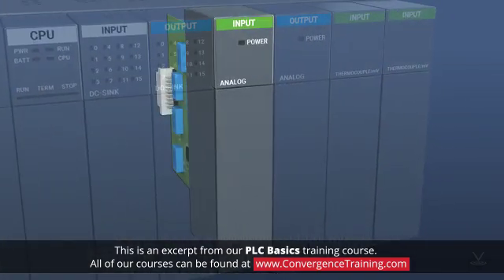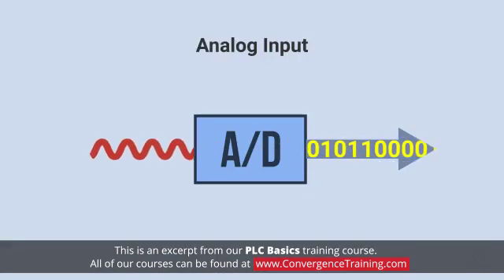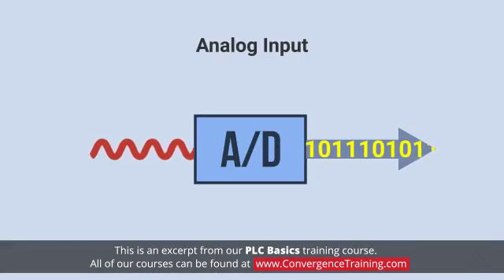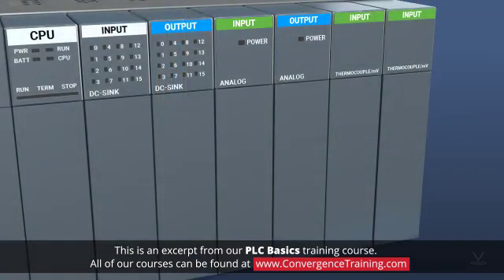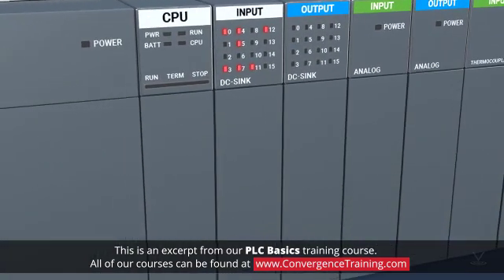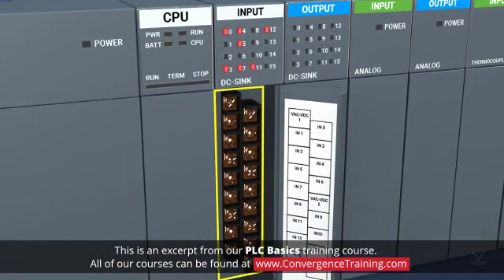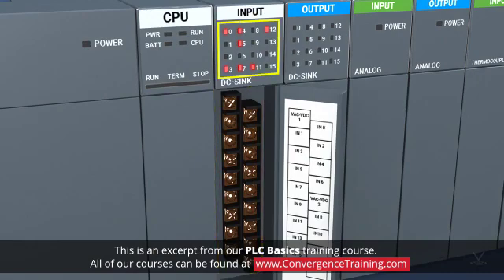While working with digital signals is a large part of what PLCs do, they can also work with analog signals. Analog input cards use A to D converters to convert electrical input signals into scaled computer-compatible digital values. Each input card has a set of input terminals and a set of LEDs that indicate the status of each input channel.